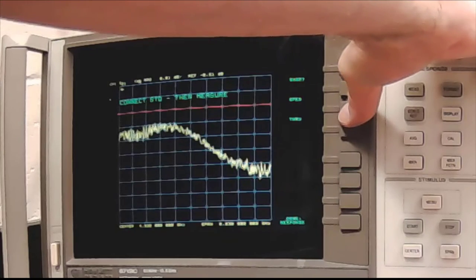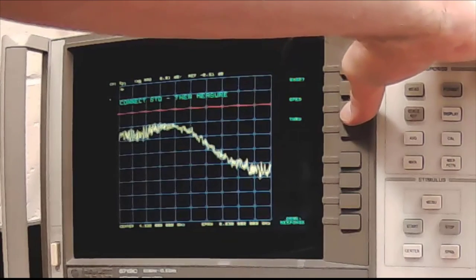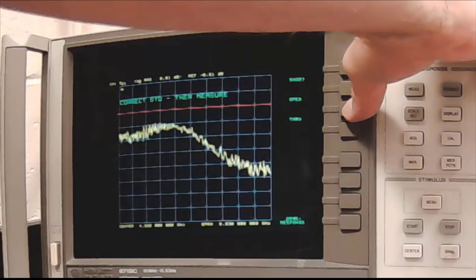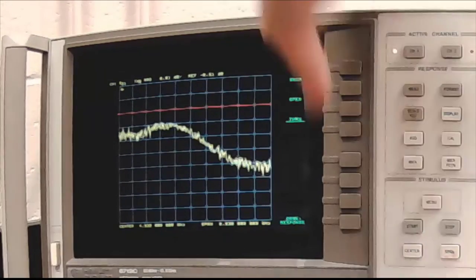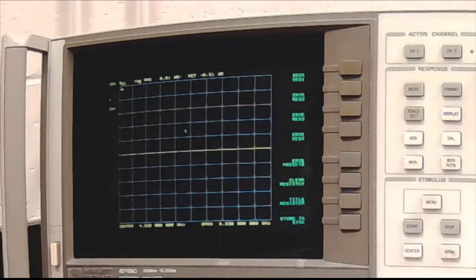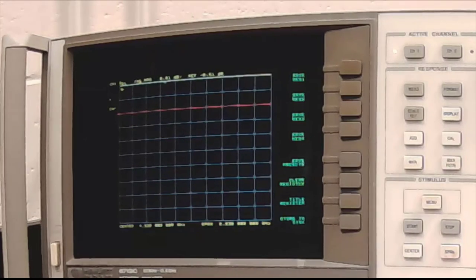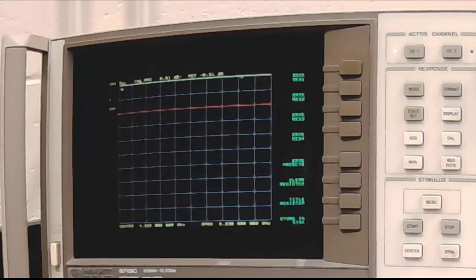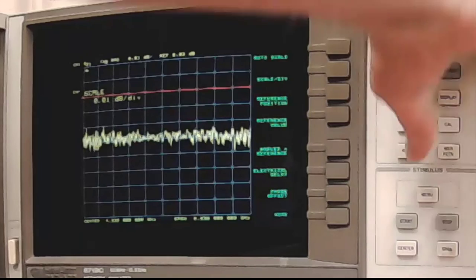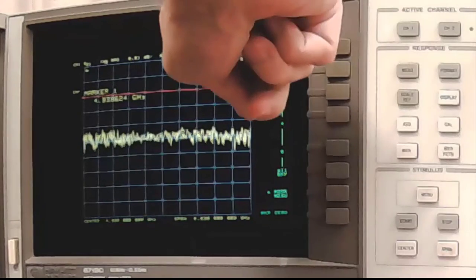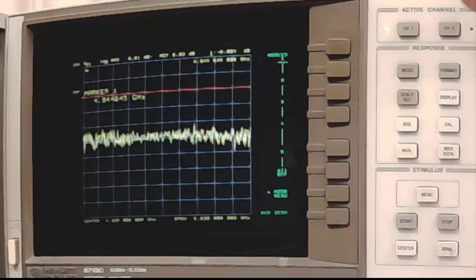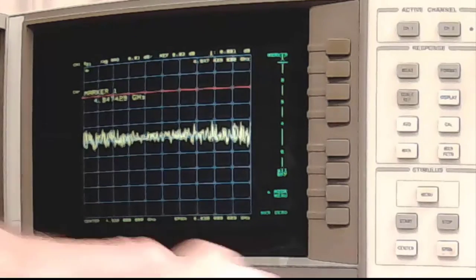Through, because I want to subtract out all of the excess insertion loss for a through measurement. It sweeps once to measure its calibration coefficients. We still haven't removed the insertion loss of the bullet. And we're not going to. If you want to remove the insertion loss of the bullet, you get yourself a calibration kit with known calibration coefficients and do it the right way. So we have zero insertion loss. A number scattered around zero is displayed for the S21 at the top of the screen.